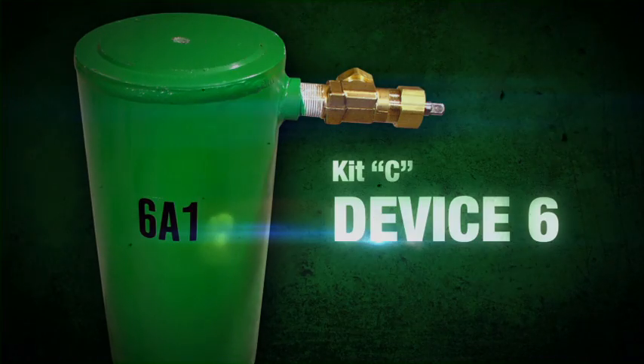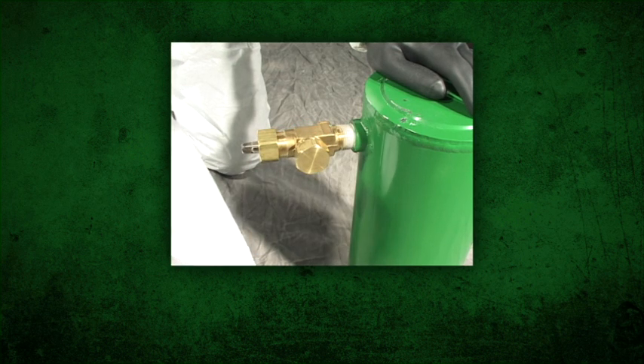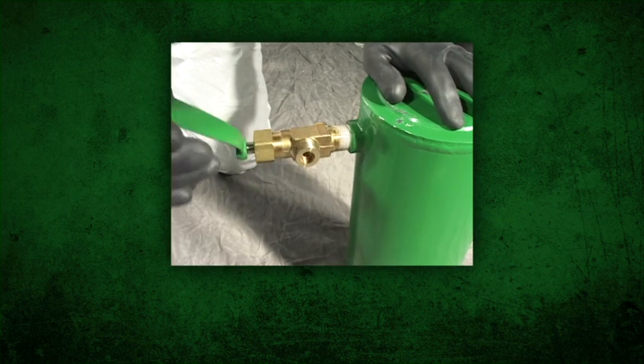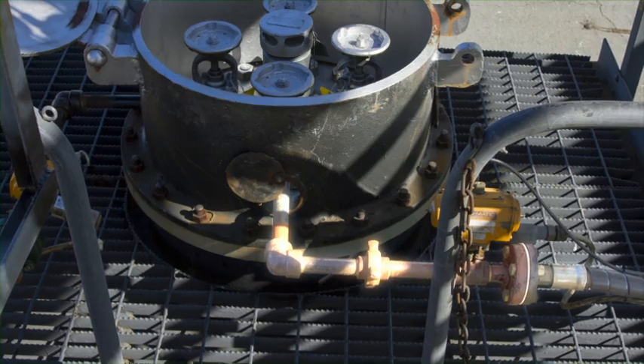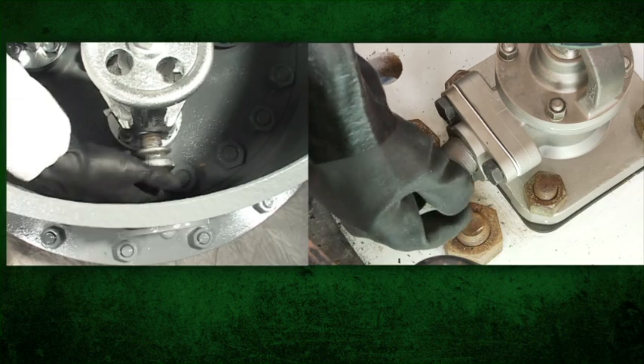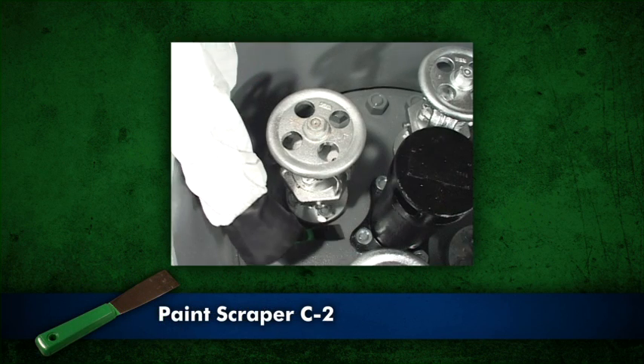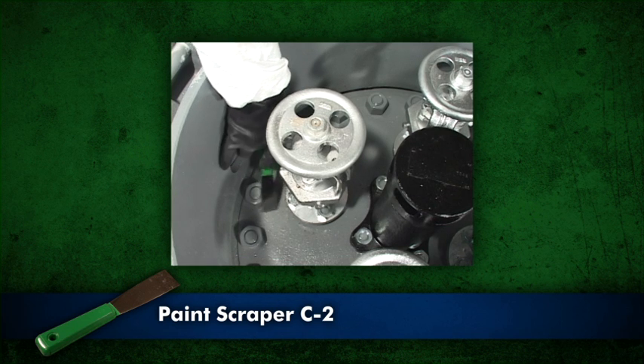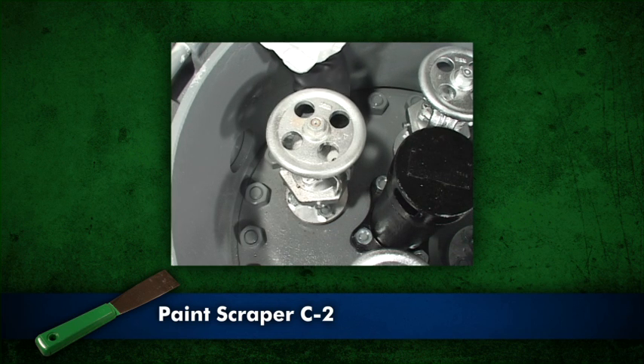Device 6 can be used to contain all leaks in and around the angle valve, including those previously identified. To apply device 6, remove the outlet cap from vent valve 6V on hood 6A1 and open the valve — this eliminates pressure buildup inside the hood as it's being installed. Disconnect any piping if the leaking angle valve is connected, or unscrew the valve outlet plug. Place the outlet plug against the packing gland. If the plug chain or cable is in the way of the hood, cut it off with bolt cutter C3. Clean the pressure plate, using paint scraper C2 if the paint is loose or uneven. The cleaner this surface is, the more likely a good seal will occur.